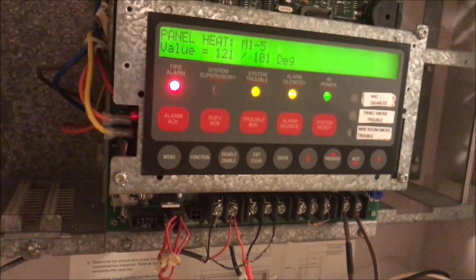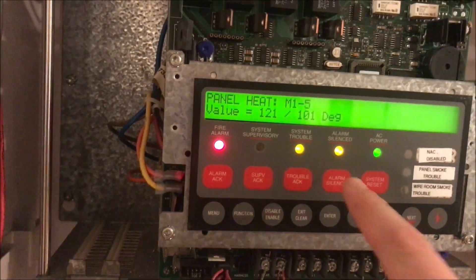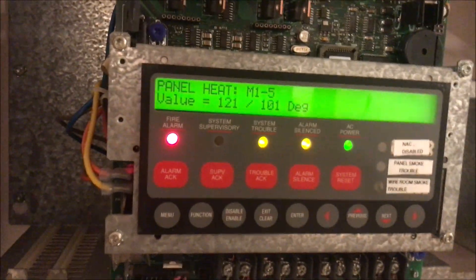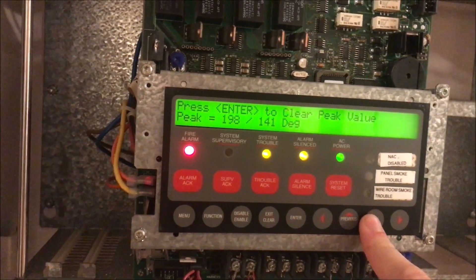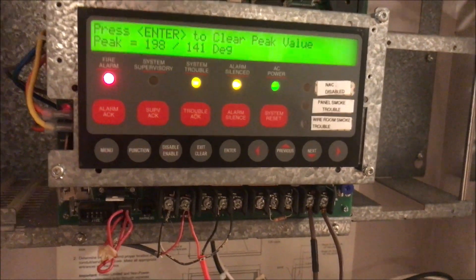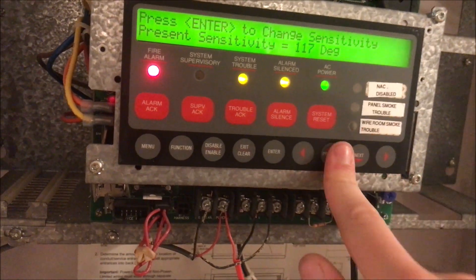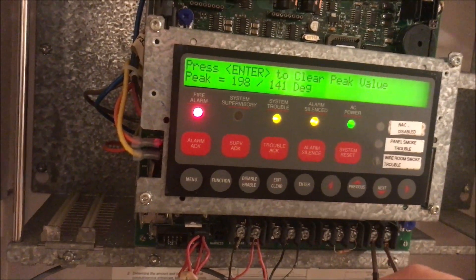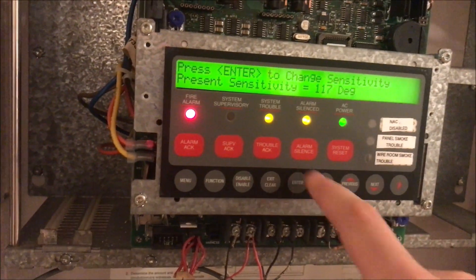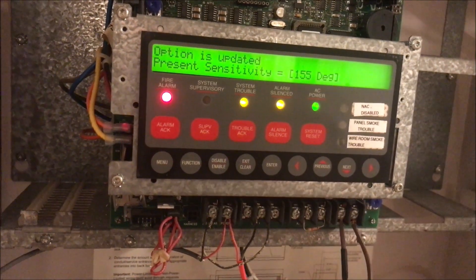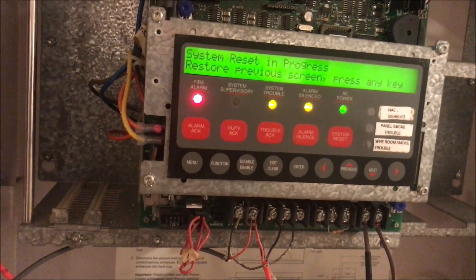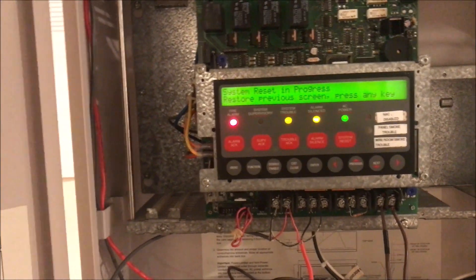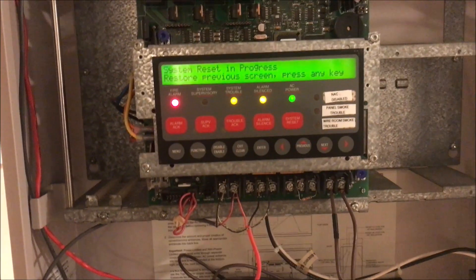It's pretty cool. You can see it's basically real-time. You can use it almost as just like a thermometer if you really wanted to - I mean, I wouldn't recommend it. We'll do this again. We're going to clear the peak value again and we're going to change the sensitivity to 155 degrees. We'll reset the system, wait for that detector to reset, and then we'll trip it again and the temperature should be higher for an activation.